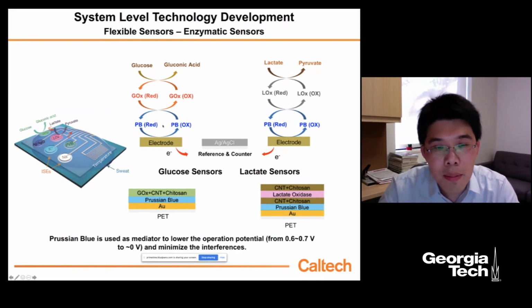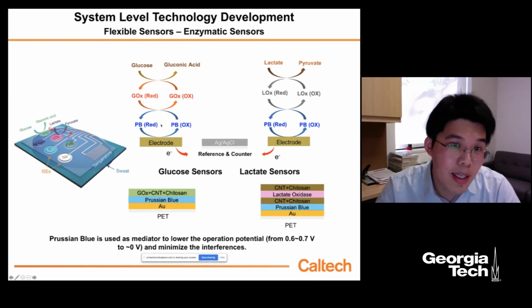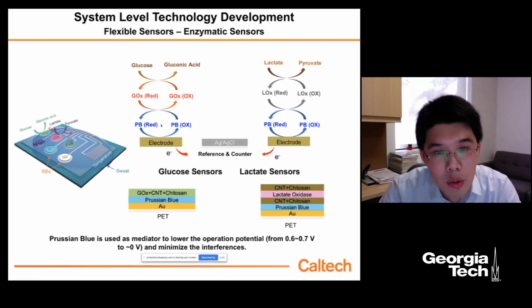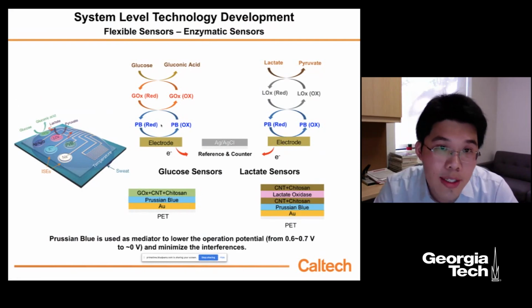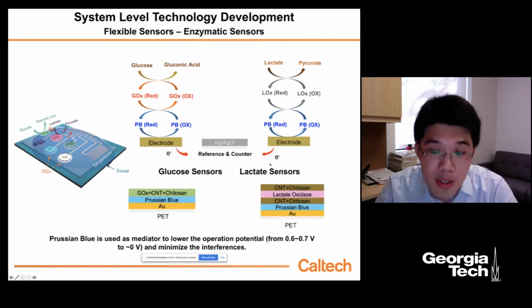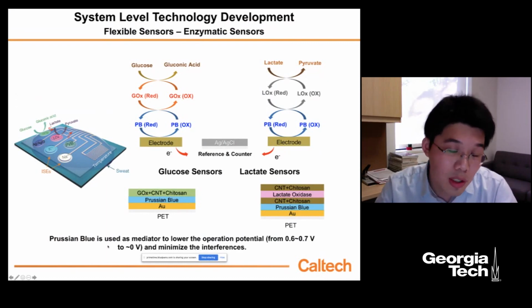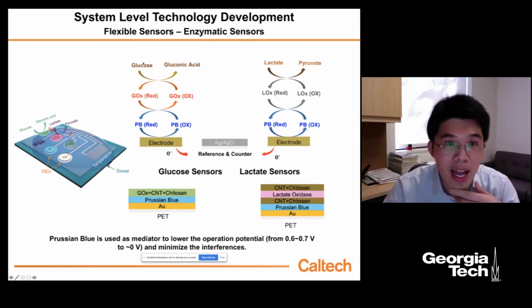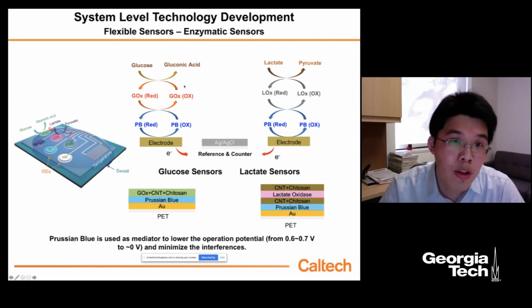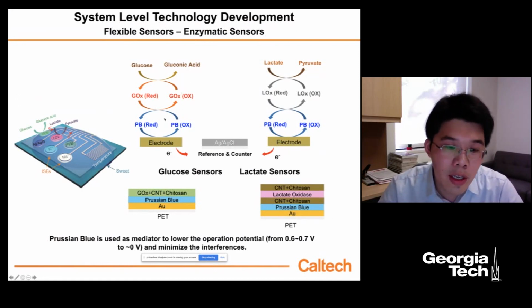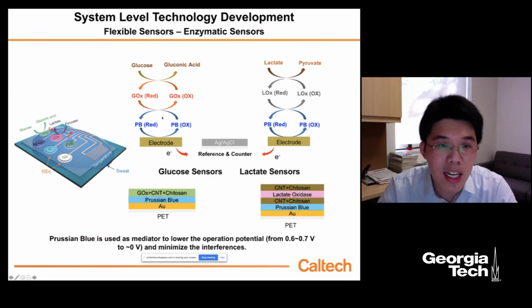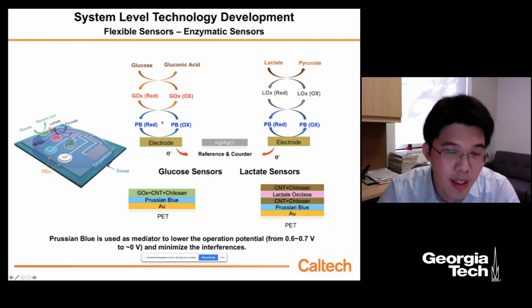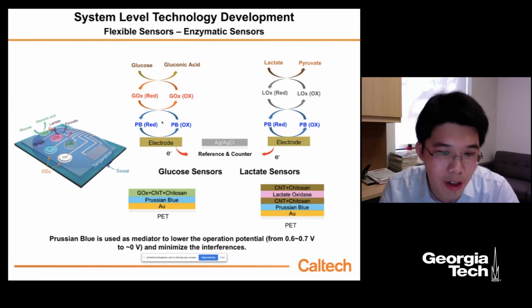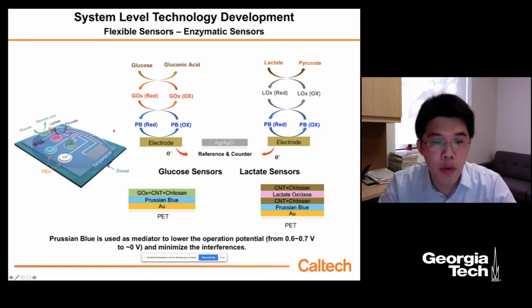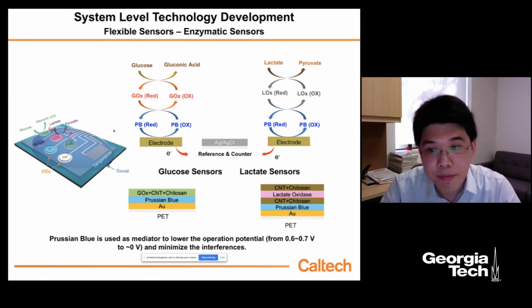For glucose sensing, importantly, we use a redox mediator. It's basically a generation 2 glucose sensor. Prussian blue, for example, is one redox mediator that can lower the glucose sensor operation voltage from 0.6 to 0.7 volt down to around 0 volt. Initially, you need to detect hydrogen peroxide, the byproduct of glucose oxidation. Right now, with Prussian blue, we only need to detect the Prussian blue redox reaction, which is roughly around 0 to 0.1 volt. The operation voltage is very low. It will minimize the interference from other chemicals.